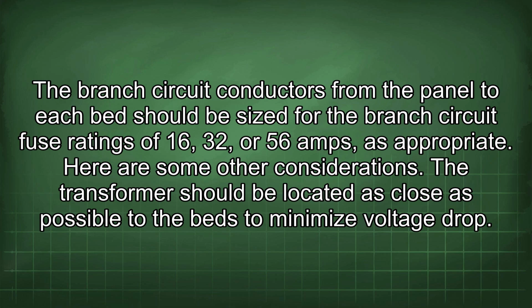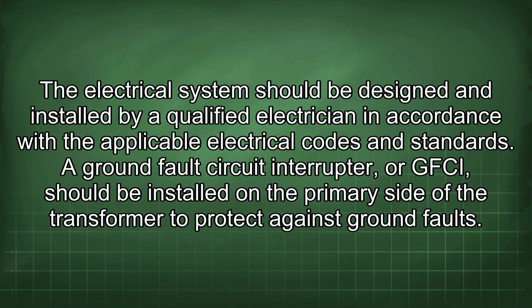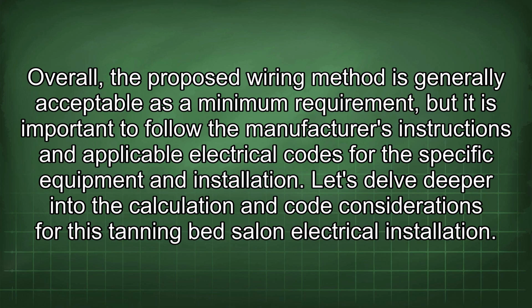Here are some other considerations. The transformer should be located as close as possible to the beds to minimize voltage drop. The electrical system should be designed and installed by a qualified electrician in accordance with the applicable electrical codes and standards. A ground fault circuit interrupter, or GFCI, should be installed on the primary side of the transformer to protect against ground faults. Overall, the proposed wiring method is generally acceptable as a minimum requirement, but it is important to follow the manufacturer's instructions and applicable electrical codes for the specific equipment and installation.